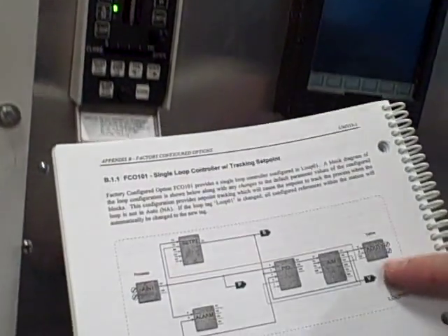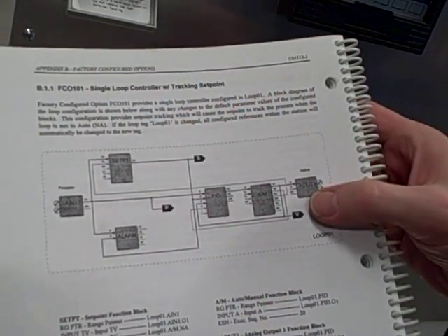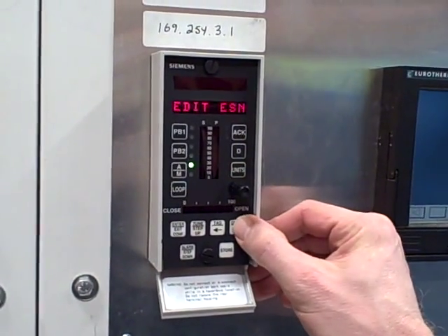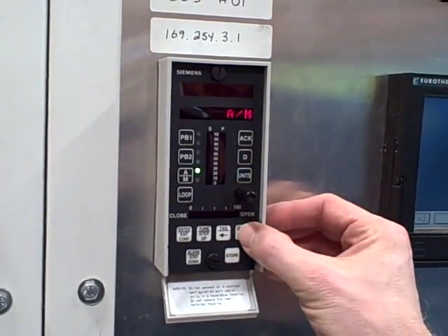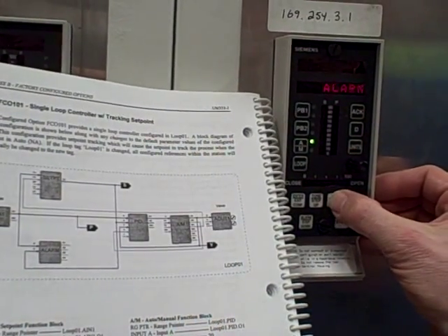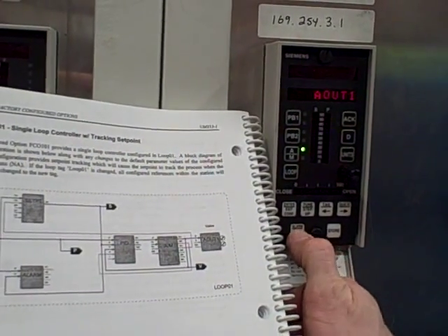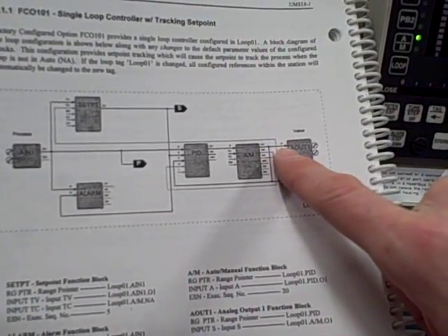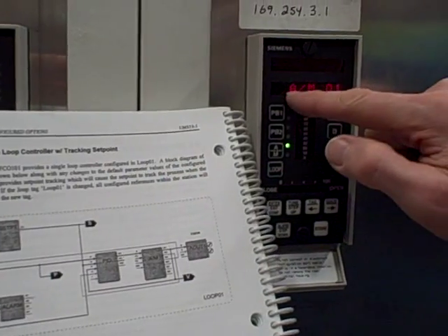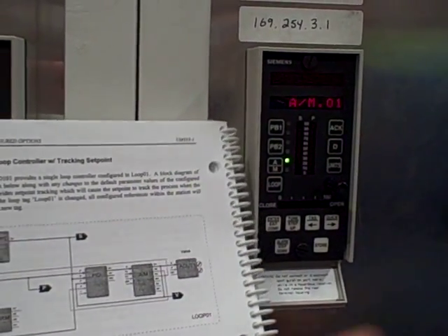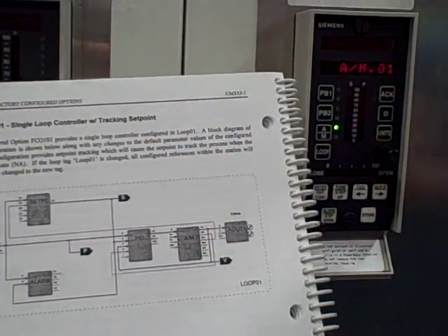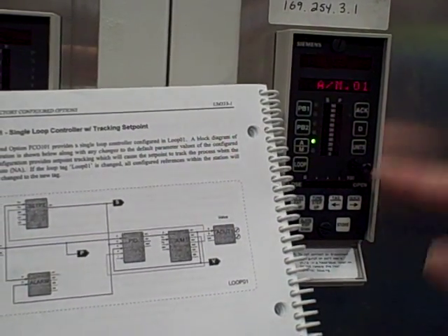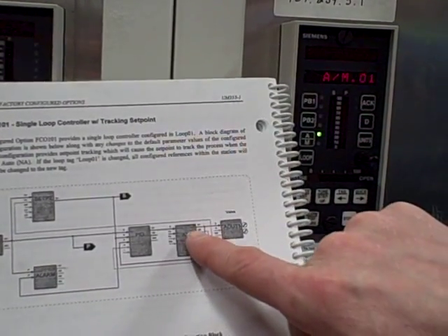First, let's investigate how this is set up in the original configuration. I'm going to descend into the menu structure and look at the parameters for analog output number 1. Entering configuration, stepping down twice, going over to 'edit function block' and stepping down. It shows all the different function blocks in this program in alphabetical order, and one of them is analog out 1. Stepping into that, I can see all the different parameters. One here is input S, which is the signal line going to that block. Stepping into that, it says input S comes from auto manual block output 01. This is how you tie the blocks together — you tell each block where it gets its input from. So analog output block number 1 gets its input signal from the output of auto manual block dot 01.